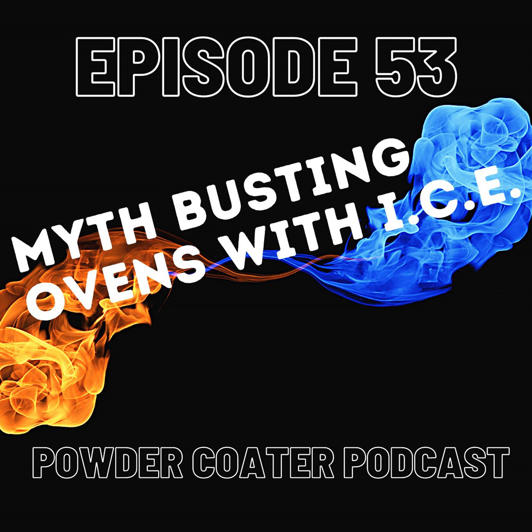So typically we'll go floor to ceiling or ceiling to floor, or we'll go side to side, sometimes depending on the part. If it's a little bit heavier part, we can kind of cheat and get some good advantage where we have the supply side on the entrance side of a process, and then the return on the opposite side. So I'm driving the heat directly into the part a little bit quicker, and then I'm allowing it to gel and mellow out on the return side. There are some little games you can play with that, but if I have the ideal situation, I like to have the duct on the floor and the return in the ceiling.